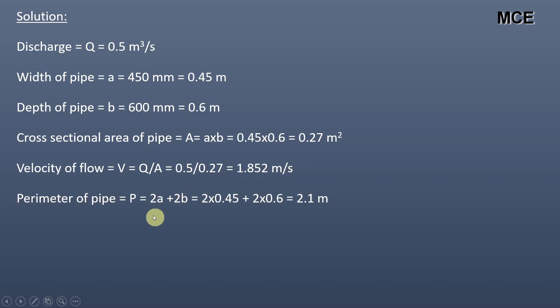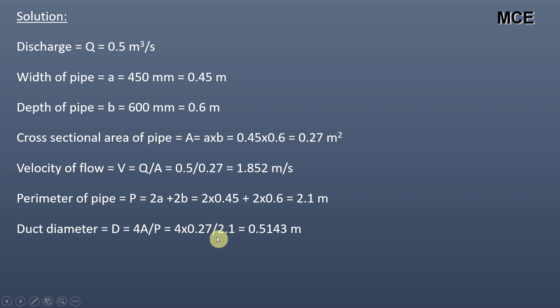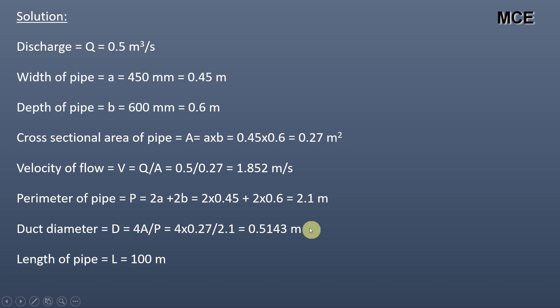Perimeter of pipe is given as twice into width plus twice into depth, which equals 2 into 0.45 plus 2 into 0.6, which is equal to 2.1 meter. Hydraulic duct diameter of the non-circular pipe is given as 4A divided by P, which equals 4 into 0.27 divided by 2.1, which is equal to 0.5143 meter. Length of pipe is given in the question as 100 meter. Kinematic viscosity of water equals 1 into 10 raise power minus 6 meter square per second.